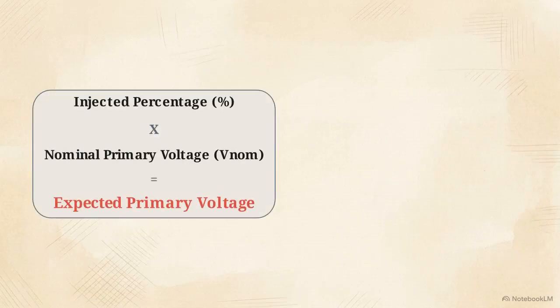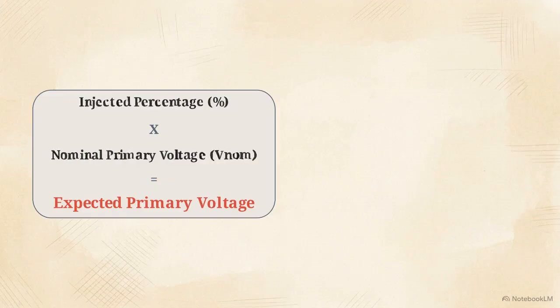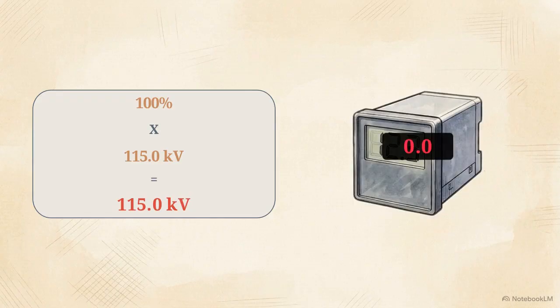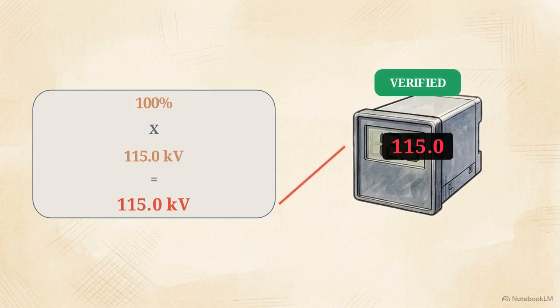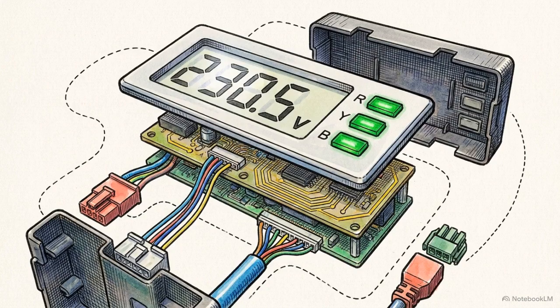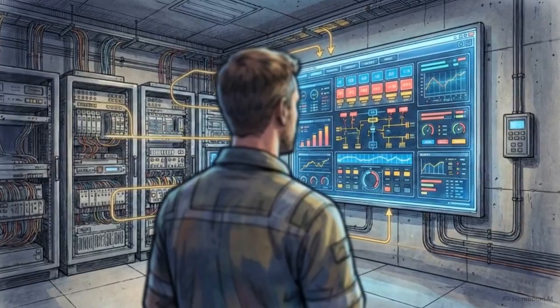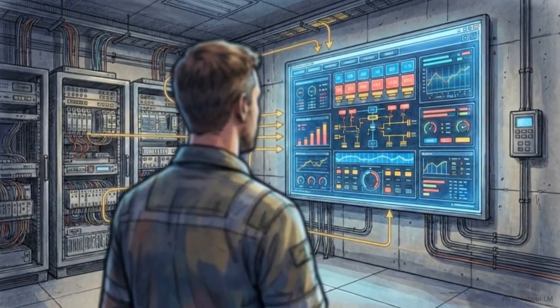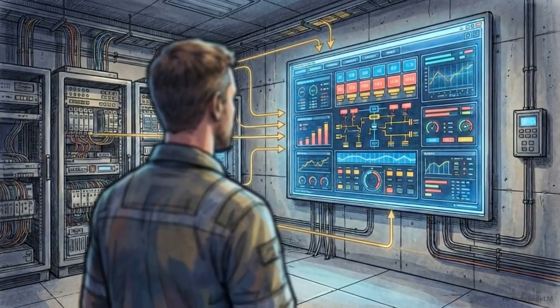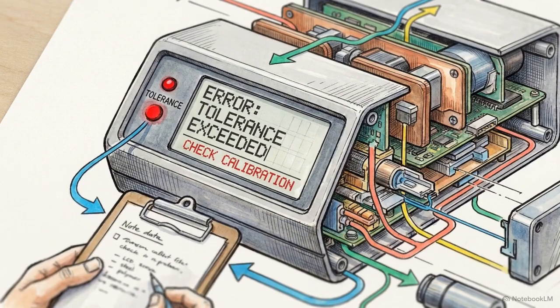As shown in this equation, you calculate the expected primary voltage by multiplying that injected percentage by the nominal primary voltage. Verify that your calculated primary voltage exactly matches the actual number displayed on the physical digital meter. While cycling through, check for any display flicker or wiring phase mismatches across all selected channels. Perfectly timed relay logic means little if the control room cannot accurately monitor the true primary scale voltage via the panel. Even with strict procedures, field discrepancies occur.